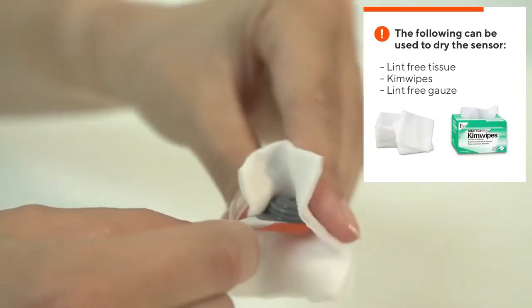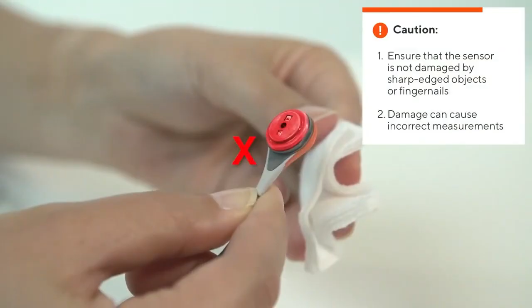After the 3-minute soak, gently rinse the sensor with clean water. Dry the grooves around the sensor with clean, lint-free gauze and make sure there is no gel residue remaining in the grooves. Gently tap the gauze on the sensor surface to dry. Do not rub the sensor surface.